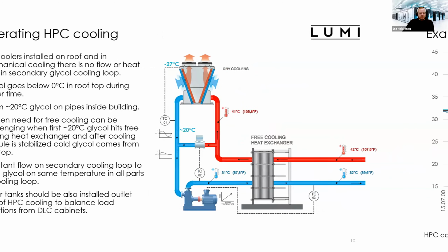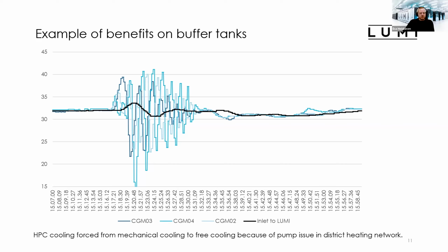And this next picture shows the case where we had to suddenly change from mechanical cooling to complete free cooling. So these are the cooling group modules 2, 3, and 4. Don't ask why we don't have 0, 1. So as you can see, when we suddenly change from heat production and mechanical cooling to full free cooling, the outlet from the heat exchangers to the Lumi started to increase, and it went in the worst case up to 40 degrees. And when this sudden cold glycol came from outside, it started to drop dramatically, and it did this swing for a while before it was balanced.